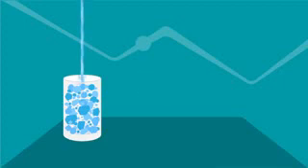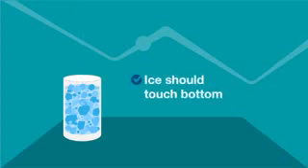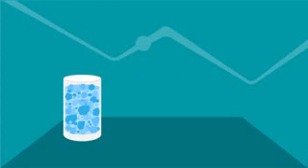Slowly add cold water until the water line is about half an inch below the surface of the ice. A correctly made ice bath should always have ice touching the bottom of the cup and not floating in the water. If there is too much water, freezing point will not be achieved, so if the ice starts to float, pour out some of the water.